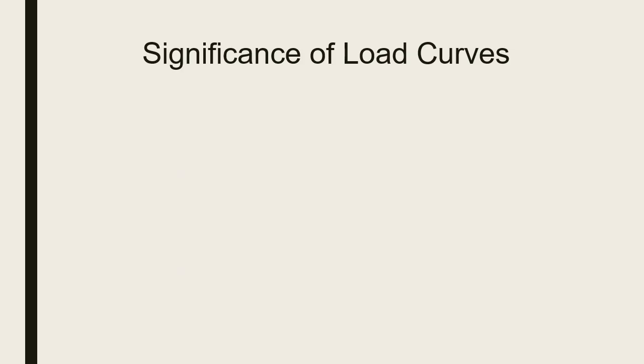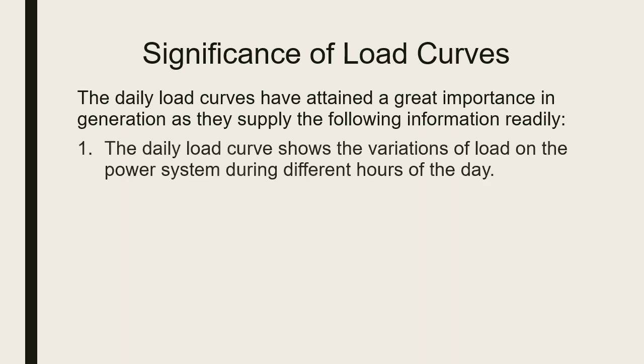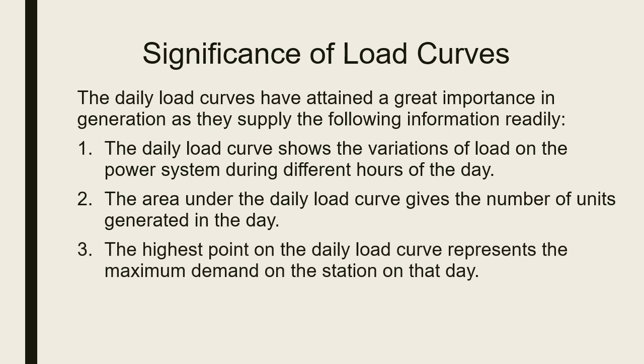What is the significance of load curves? The daily load curves have attained great importance in generation as they supply the following information readily. First, the daily load curve shows the variations of load on the power system during different hours of the day. Next, the area under the daily load curve gives the number of units generated in the day. Next, the highest point on the daily load curve represents the maximum demand on the station on that day.